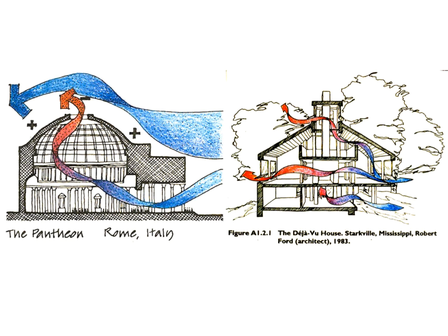Moving on to stack ventilation — here are two examples, one more contemporary on the right and one more classical on the left. In stack ventilation, the section is critical, whereas cross ventilation relies on open plans with an inlet on one side and an outlet on the other driven by wind pressure. In stack ventilation, air must move from low to high through the section, driven by the height difference between inlet and outlet — the stack height. Importantly, stack ventilation is not dependent on wind speed, so it works 24/7 whenever the building has a heat gain.